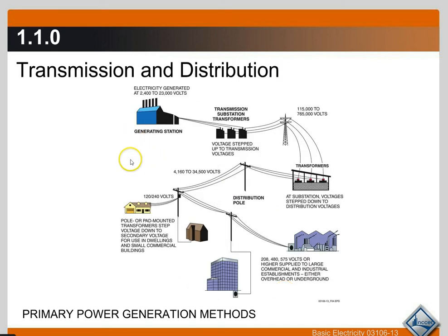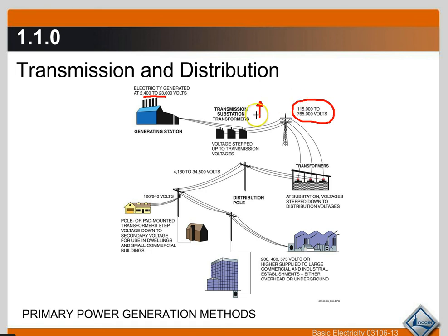So we take our primary generators — we have those windings turning inside of the magnetic lines of force — and it starts out, depending on how it's generated, between 2,400 and 23,000 volts. It goes to a substation sitting right near the generating station, and it goes through transformers which step that voltage up to a higher voltage so that they can transmit this electrical power through miles and miles of wire. They step it up considerably — from 100,000 up to almost a million volts, depending on the design and the length of the transmission wires.